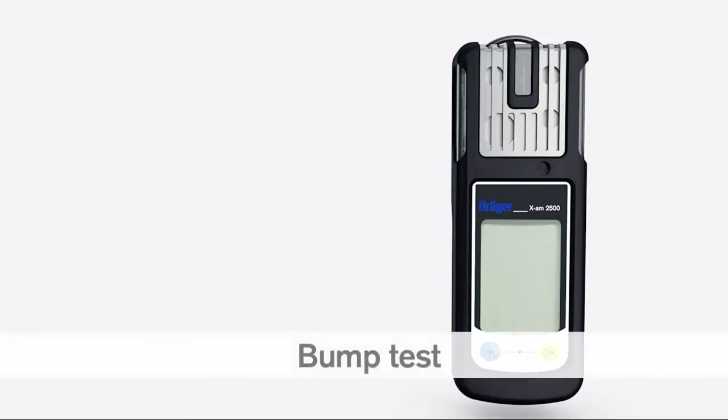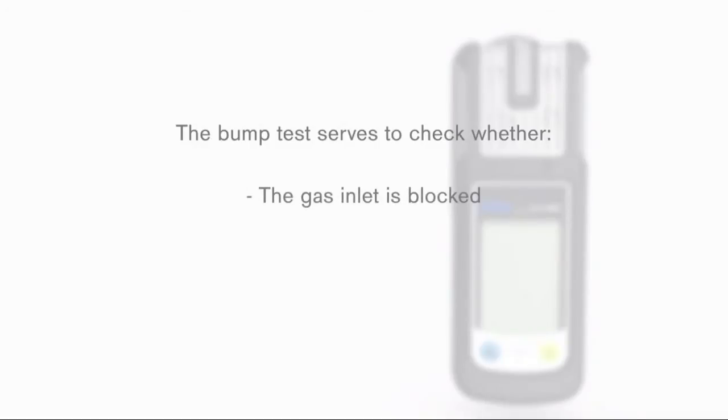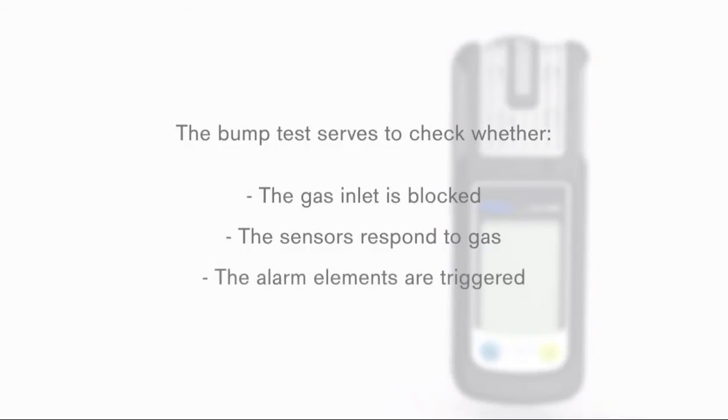You must carry out a bump test of your Draeger X-am 2500 in accordance with the national, state, local, or company regulations and guidelines in force. The bump test serves to check whether the gas inlet is blocked, whether the sensors respond to gas, and whether the alarm elements are triggered.